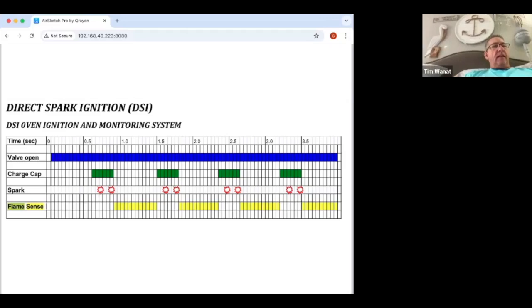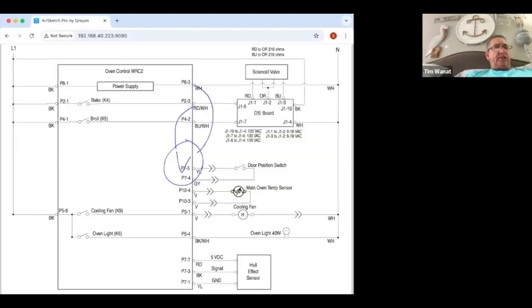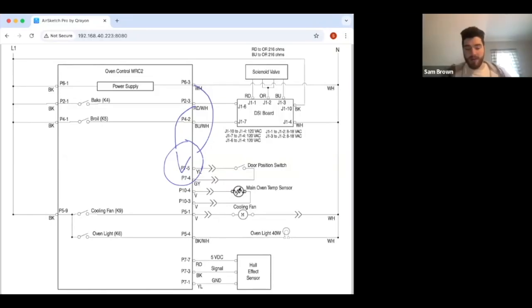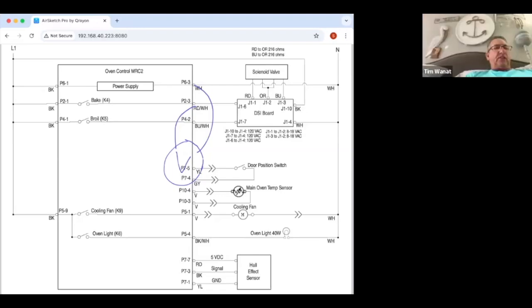So again, the fix on this one was to replace the board. They didn't replace the sensor as well, correct? No, the temperature sensor was in spec, so there was no reason to replace it. I guess I'm just trying to think that would be the only outside component making a decision to maybe stop the solenoid valve, it's going to shut off because...